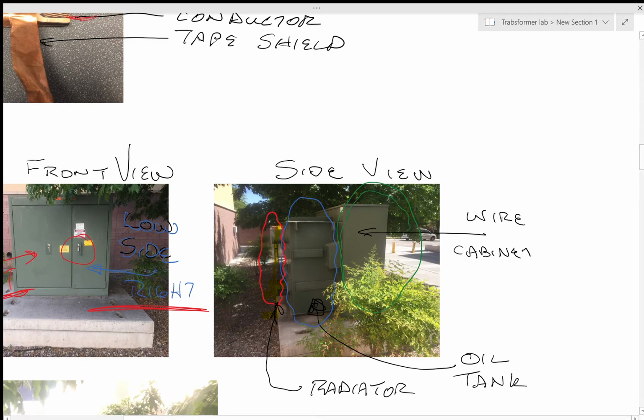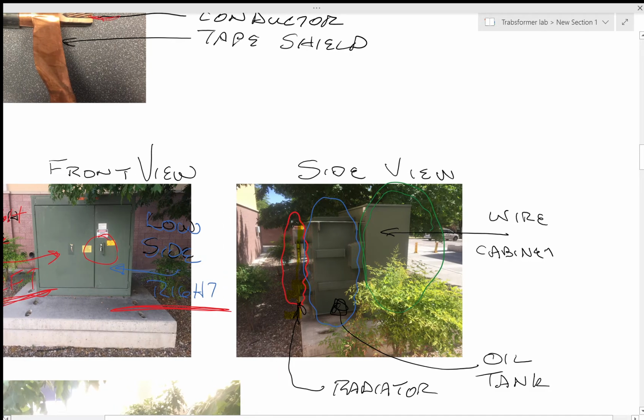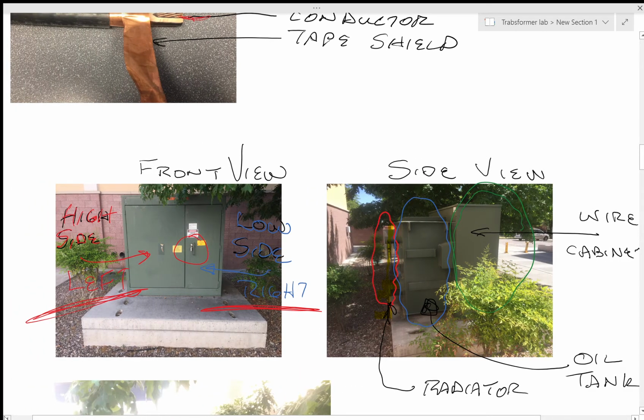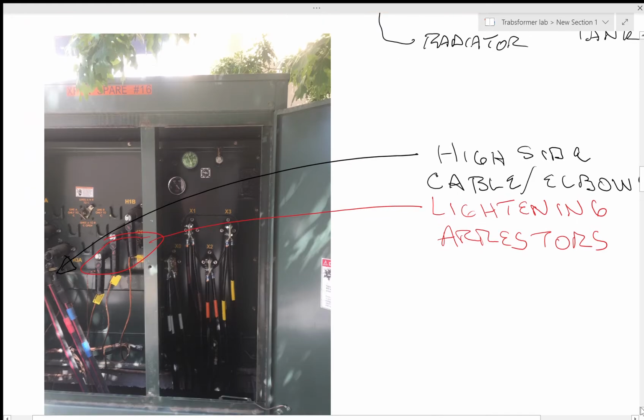So the different parts, if you remember on the video that you saw, the terminators were coming out of the top of that one on the video. You have to open the doors on this one to get to the terminals of the transformer. So different types of transformers, but if it's a cabinet type, or a pad mount, which is what this is, pad mount with an internal terminator cabinet, then the high voltage side is always going to be on the left, and the low voltage side is always going to be on the right. So here we go, some more. All right, here's the open doors.